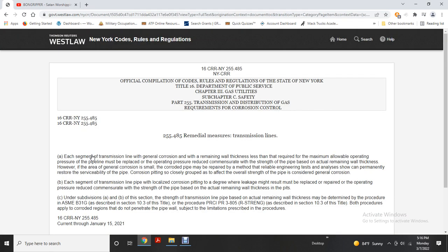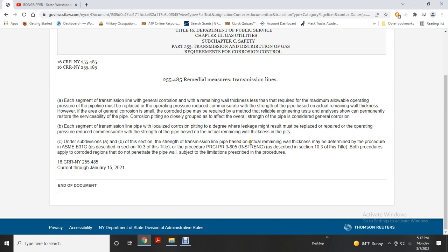Remedial measures for transmission lines: each segment of transmission pipe with general corrosion where remaining wall thickness is less than that required for the maximum allowable operating pressure must be replaced or have the operating pressure reduced commensurate with pipe strength. Where the area of general corrosion is small and the corroded pipe has substantial remaining wall thickness, the pipe may be repaired by a method that reliably restores serviceability. Corrosion pitting so closely grouped as to affect the overall strength of the pipe is considered general corrosion. Each transmission pipe segment with localized corrosion pitting to the degree where leakage might result must be replaced or repaired, or the operating pressure reduced based on actual remaining wall thickness in the pits.